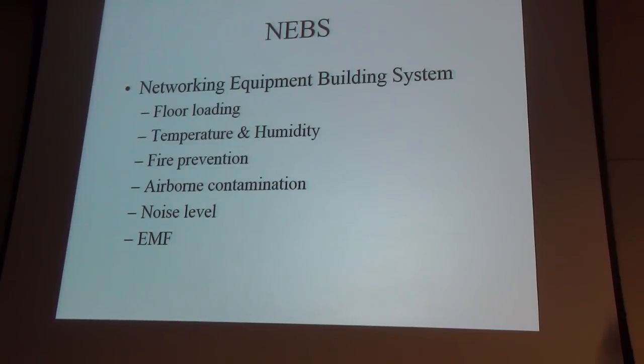Airborne contamination is a real concern. True story: in 2001 at General Motors Warren Tech Center, we had a basement that got flooded, and two or three disk drives were failing every day in every server rack. After a month and a hundred disk drives replaced, they asked what was going on. People were opening doors, drilling, smashing walls, and all sorts of dust was coming in. A plastic curtain doesn't stop it. This contamination gets inside disk drives and causes failures.